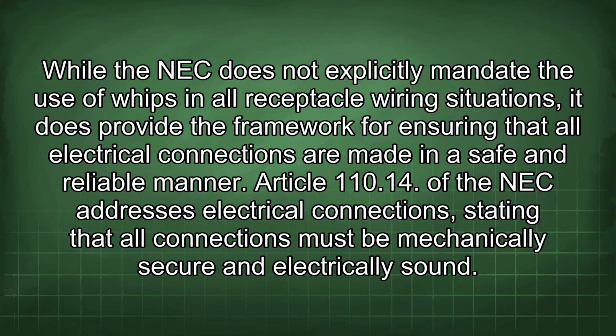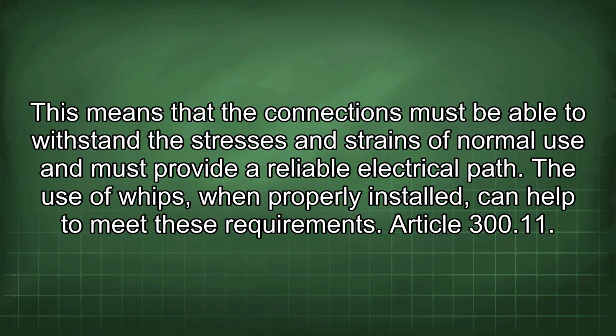Article 110.14 of the NEC addresses electrical connections, stating that all connections must be mechanically secure and electrically sound. This means that the connections must be able to withstand the stresses and strains of normal use and must provide a reliable electrical path. The use of whips, when properly installed, can help to meet these requirements.